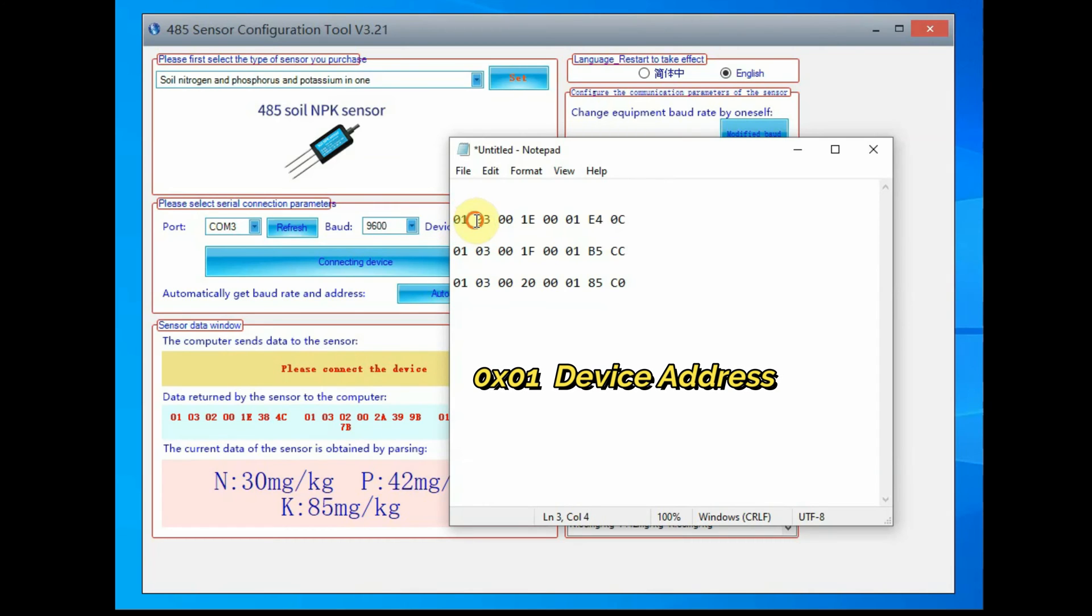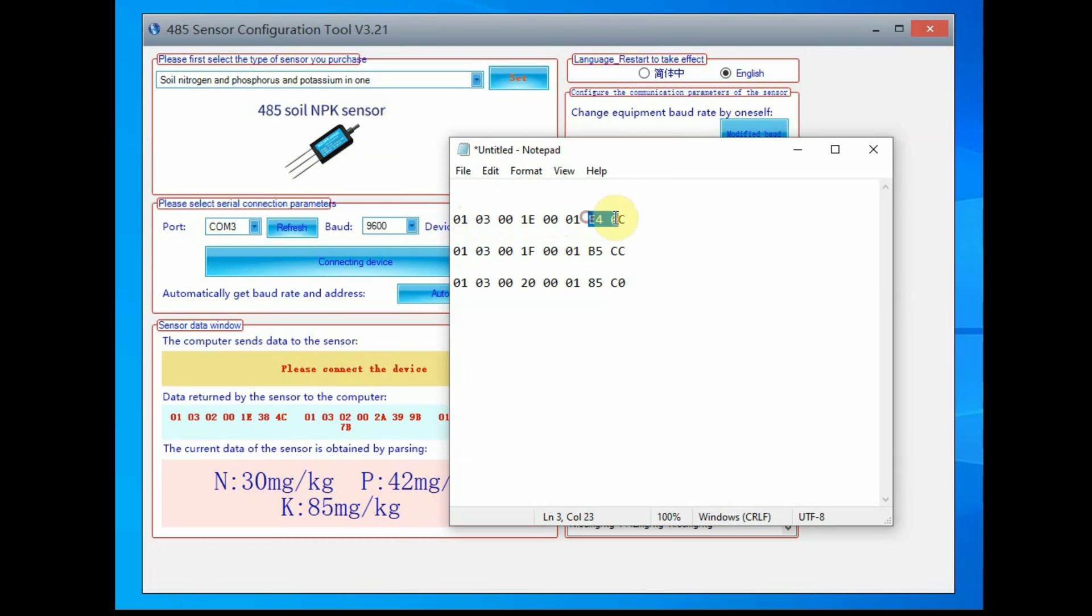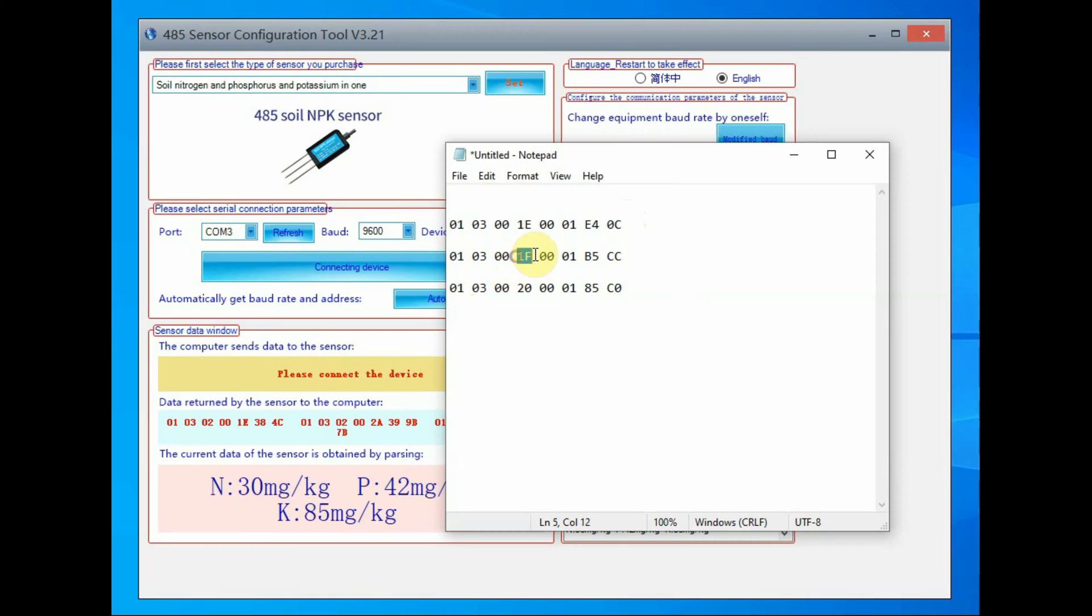The 0x01 is the device address and 0x03 is the command, that is reading holding registers, and then two bytes 0x001E is the starting address, and then 0x0001 is the number of registers to read, and finally the cyclic redundancy check code, two bytes.